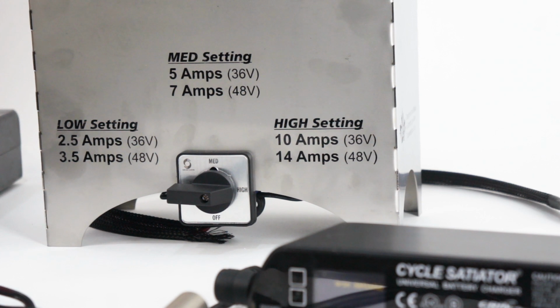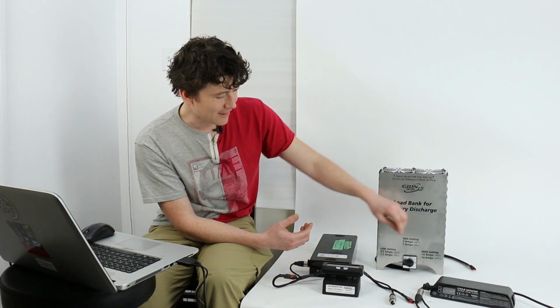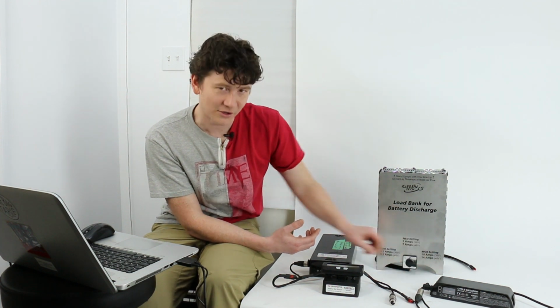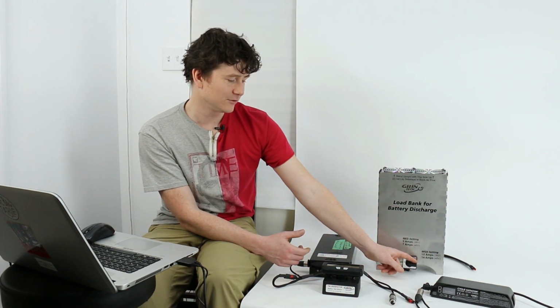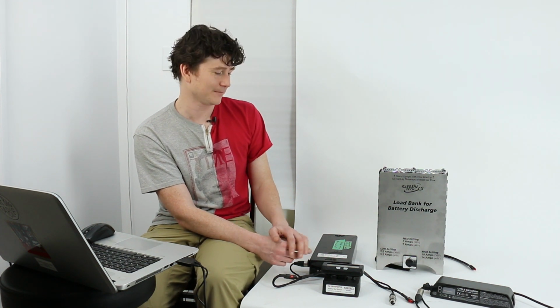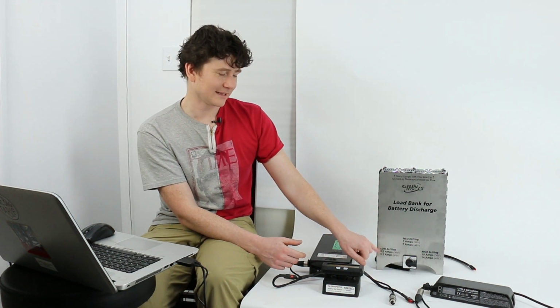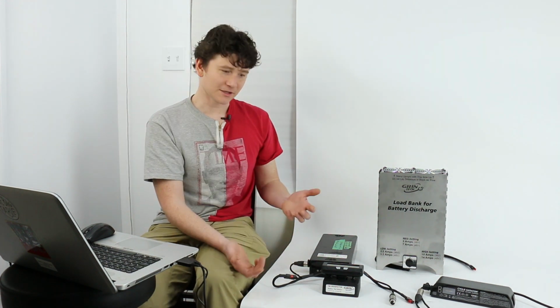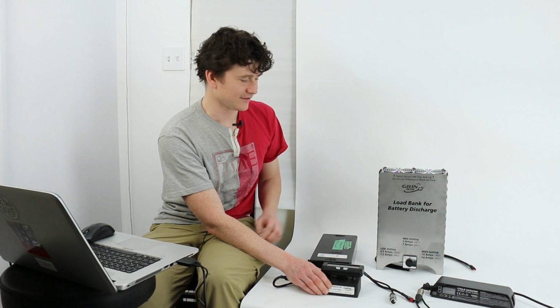This will work up to 52 volt battery packs, no problem. If you want to test 72 volt batteries, you must have this in the low setting. If you run 72 volts in either of the other settings, you will burn up and overheat the resistors and make a stinky mess. But in the low setting, this will do a 5 amp discharge with a 72 volt battery pack.